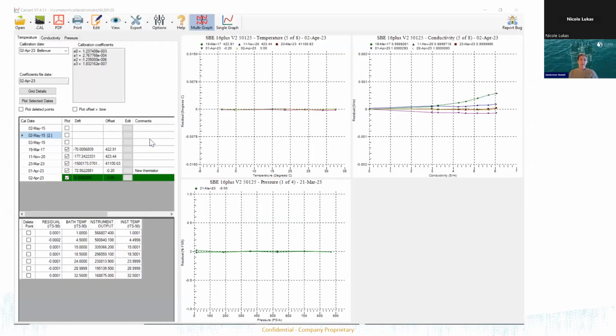So again, this step is important. If there's anything that is not performing well about the instrument, this is where we're most likely to find it. That is a really tightly controlled bath. It is capable of maintaining temperature to 100th of a degree C. And it is extremely helpful, even more helpful than something like a thermotron or anything that we can do in air or on the bench, for understanding, is your instrument still performing precisely the way that it needs to? So this is typically the step where we would find subtle problems in terms of your instrument's performance, or larger problems. The big ones sometimes manifest and are obvious. You might have called them out, but smaller problems need this type of instrumentation to really view and understand.